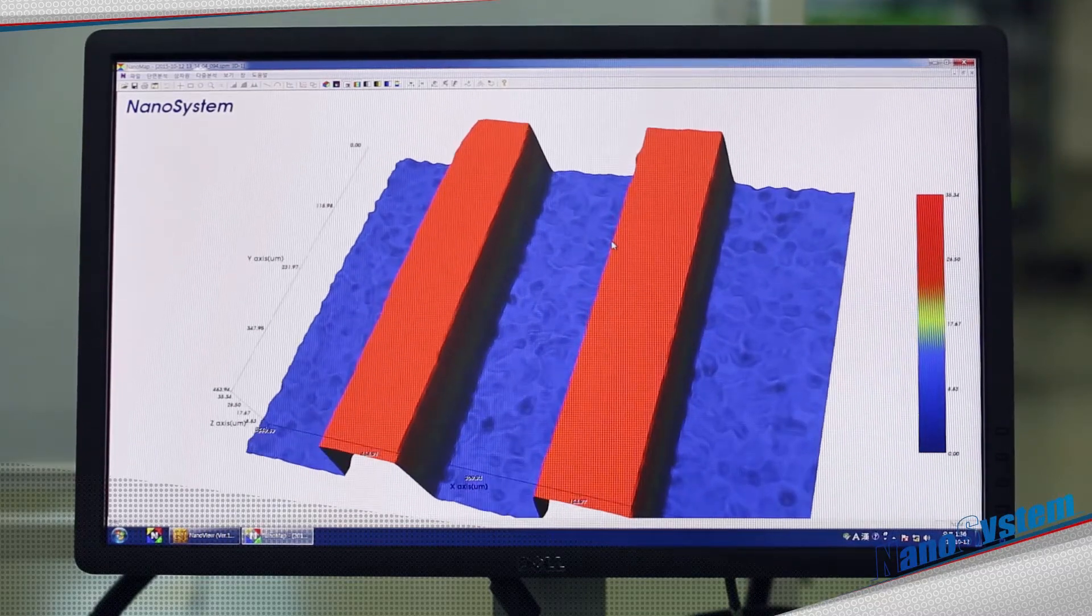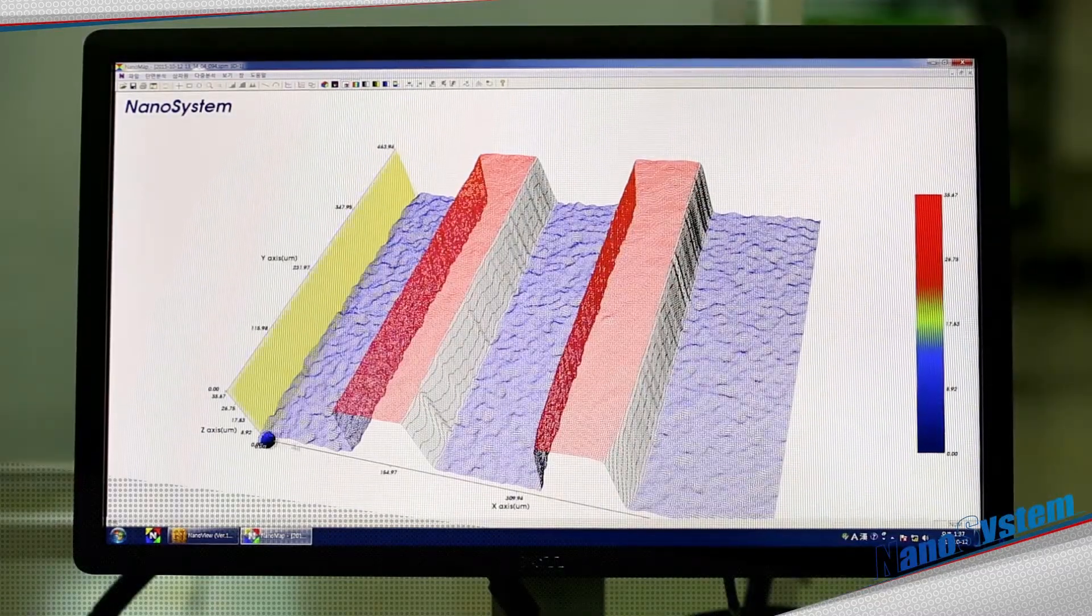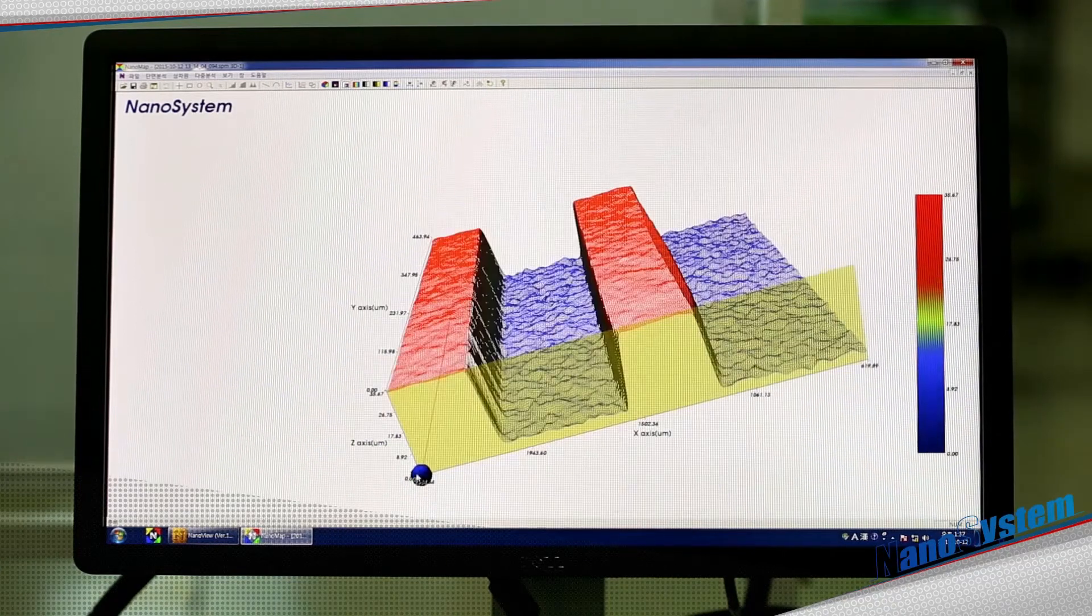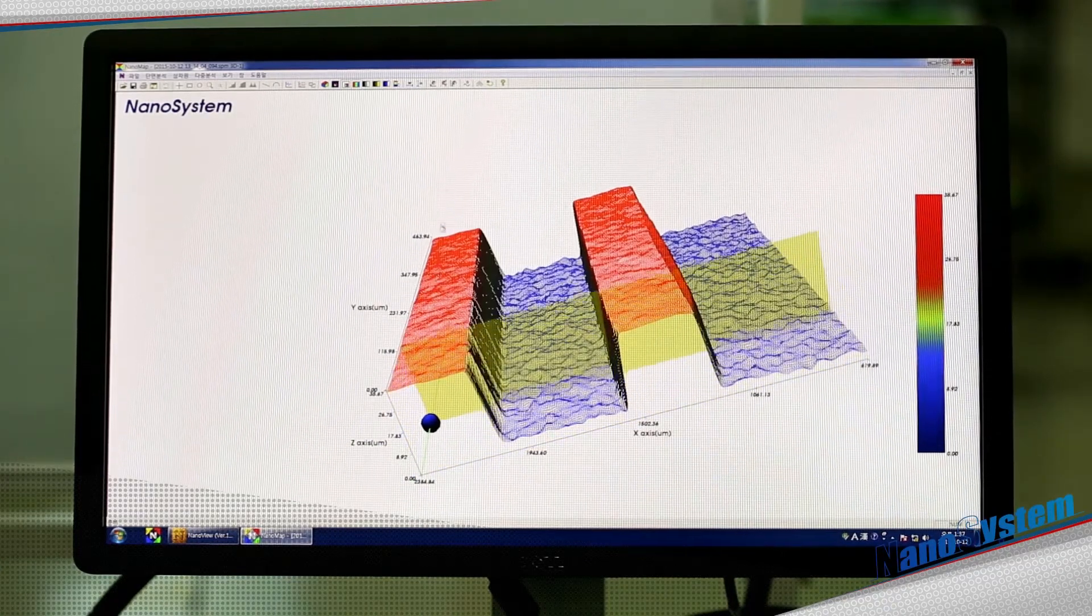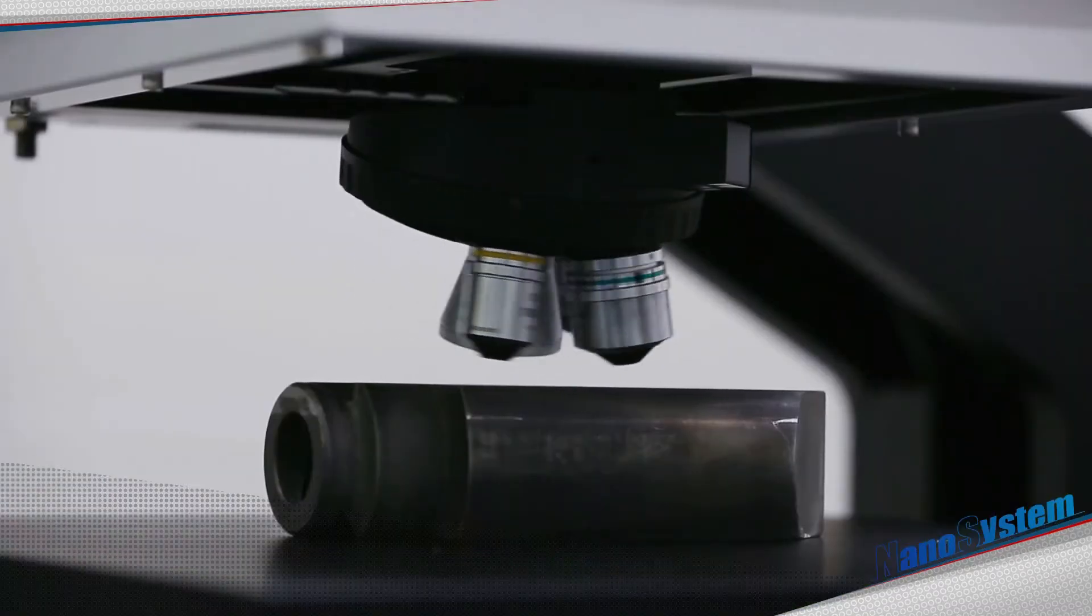Plus, repeatability is lower than 1%, 3 sigma, and regardless of magnification, Z-axis resolution is 0.1 nanometers.